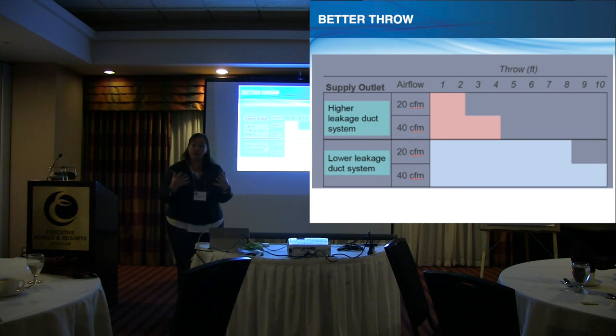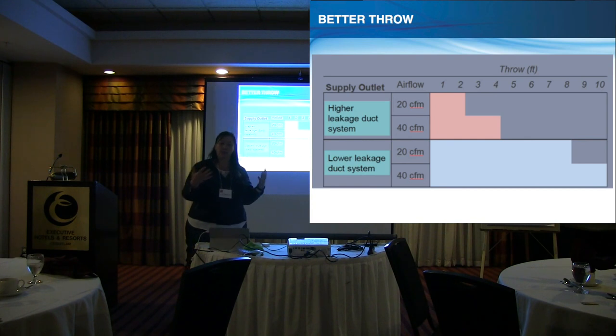But then it's also that fine line between turning into a high velocity system, that builders said we don't want high velocity systems. So we knew we needed to design a system to keep the static pressure down. So the average static pressure for a high V system is 1.2. Our static pressure is an average of 0.68, so low to medium velocity paired with equipment modulating, running at low CFM, longer cycles.